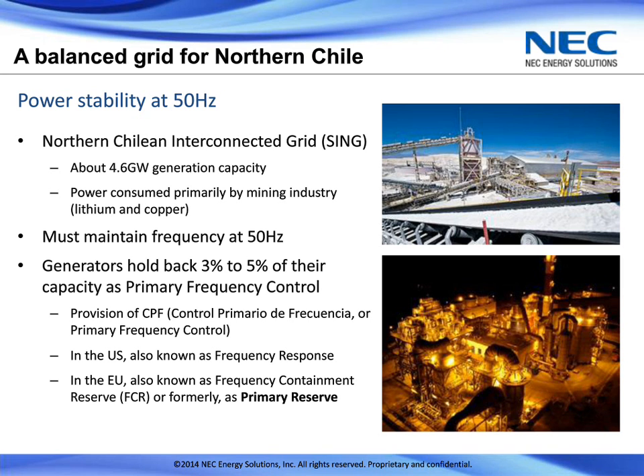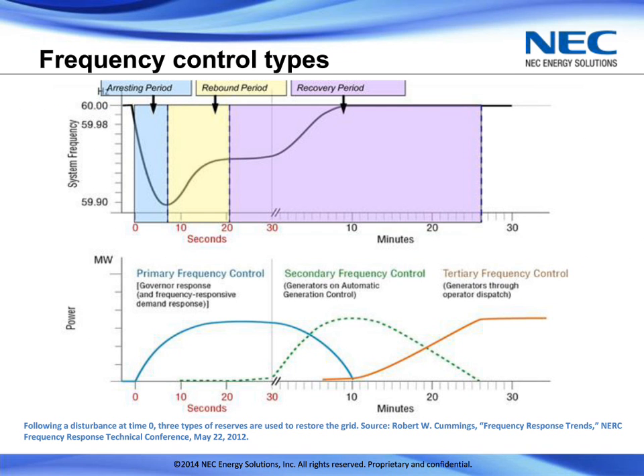So what is that function, actually? What I'm showing here are some of the different frequency control types that are out there, ways to stabilize the frequency on the grid. As you can see, there are different time scales for response to a disturbance in the frequency. There are seconds response in the first few seconds after disturbance, and there are responses that take place in several minutes or even tens of minutes after the disturbance. What we're going to be talking about today is primary frequency control.